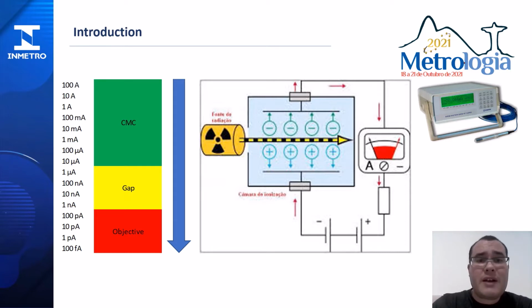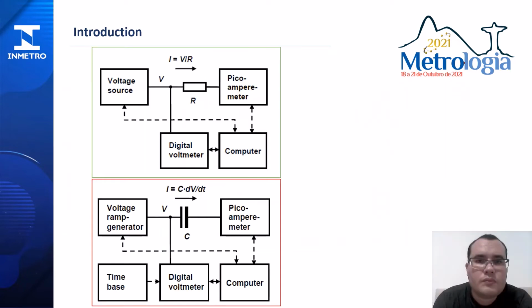This work provides an option for a calibration system from 20 microamperes to values in the order of a few picoamperes. The main objective is to serve the dosimetry area through the calibration of electrometers, especially in direct current in the range mainly between 1 picoampere and 10 picoamperes. The BIPM recommends three different methods for realizing the magnitude of electrical current.